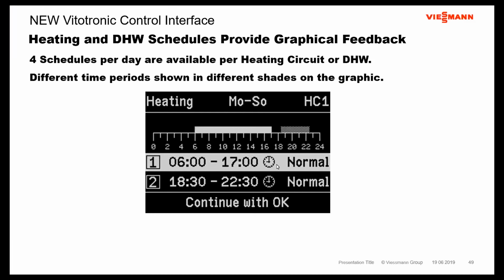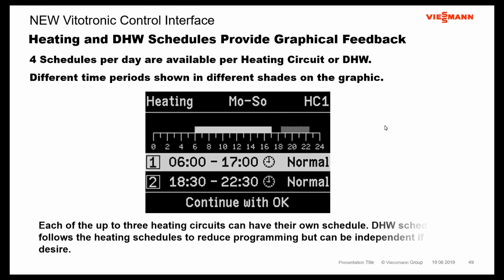But certainly in things like fan coils and high temperature baseboards, et cetera, you could utilize these timer programs and really start to extract some efficiency out of these boilers by putting them on the same type of schedule you would with a regular old thermostat.